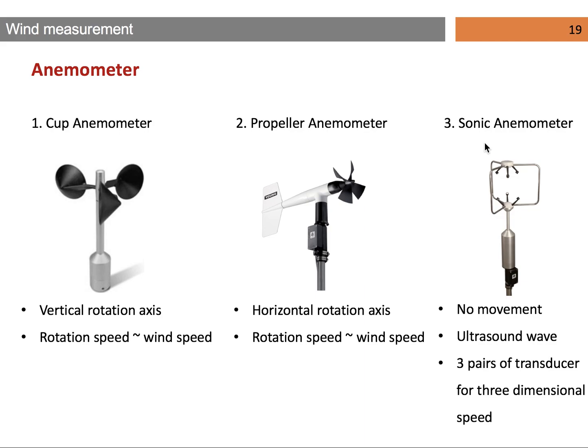And the third anemometer is sonic type. Here, the main difference of the third one compared to the first two types is that there's no movement. Here they use ultrasound waves, and they use three pairs of transducers. The transmitter will generate a sound to the receiver, and in fact, the wind will impact the process of receiving the signal. So based on that, they can calculate the speed and also the direction of the wind. The reason to use three pairs of transducers is to measure the wind speed in three dimensions.